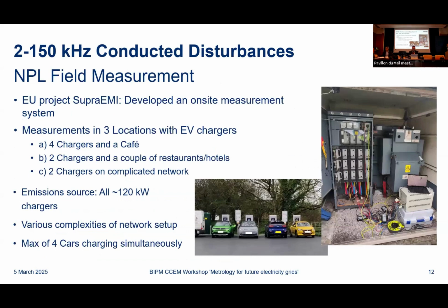So yeah, at NPL, as I said, we had this research project where we've developed an on-site measurement system. And we've implemented this CISPR-16 method, and we've taken that system out to do some field measurements, really with the objective of starting to get an idea of what the emission levels or the disturbance levels are that currently exist in the grid, because it's not something that any of the utilities are really monitoring consistently yet.